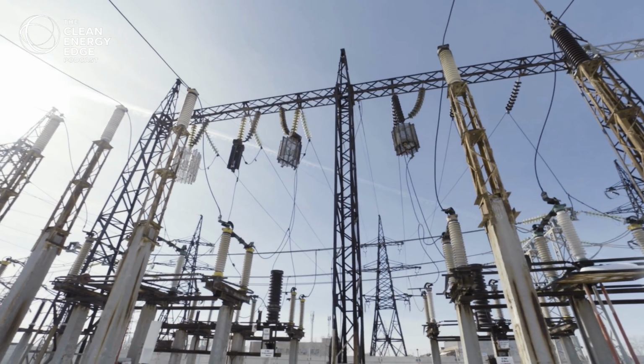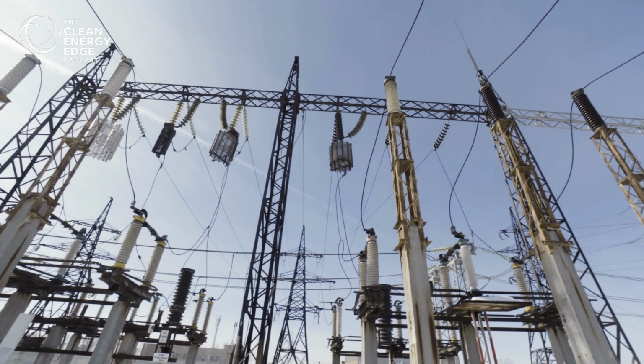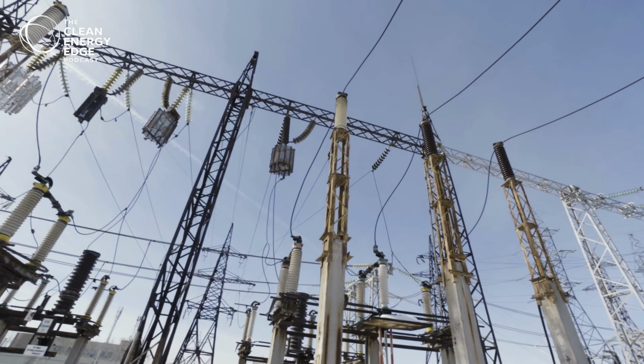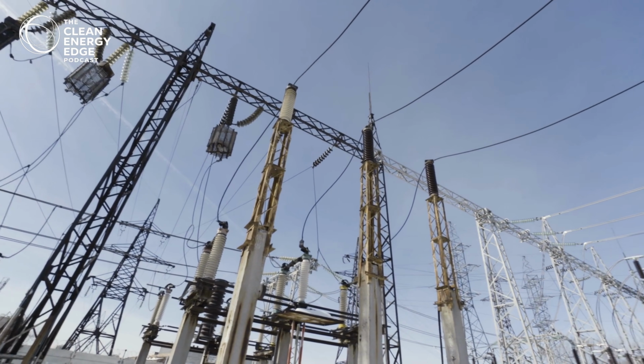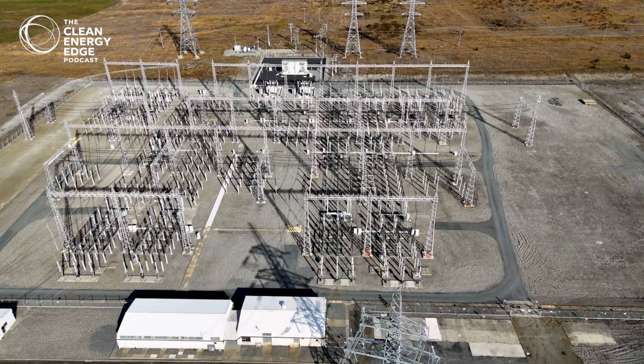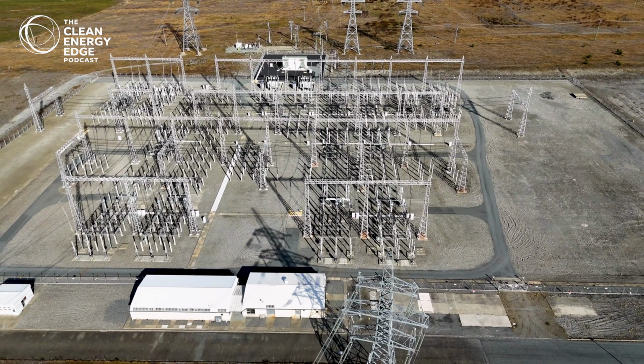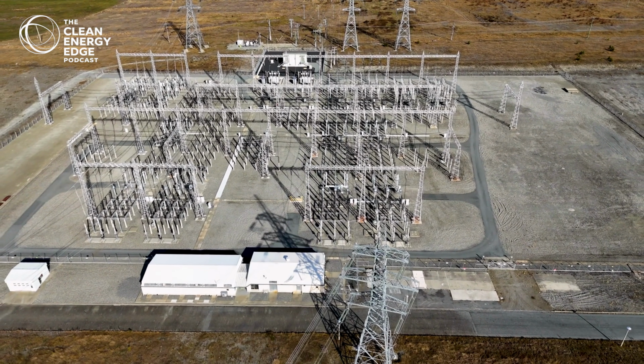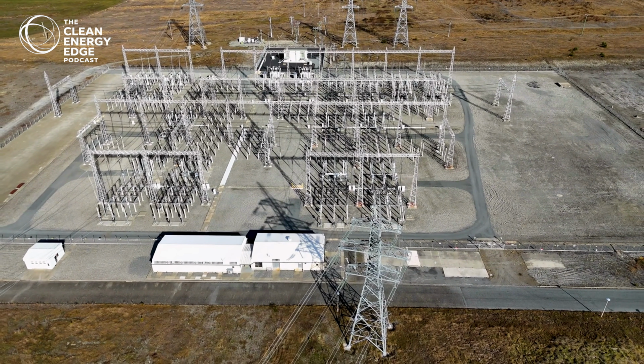Great question. There are a couple different ways substations come into the mix, specifically with interconnections and data centers. When we're talking about a data center interconnection at the substation, we could look at it from the perspective of the existing transmission grid. Let's say you're connecting into one of the RTOs or ISOs, like a PJM. They have to be able to supply that power to wherever you're proposing to interconnect with that data center. So everywhere connected within general local proximity to that interconnection, all of those substations are impacted.